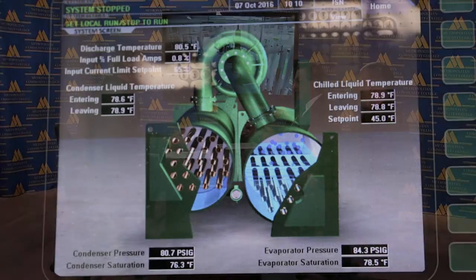And these rotate, therefore they don't wear out. That's correct, they're called maglev chillers, magnetically levitated, and it has one moving part with no friction. So they're called frictionless magnetic drive chillers, and they really perform well at part load operation, where we can reduce the speed and take advantage of the efficiency of the machine. Talk about state of the art here.